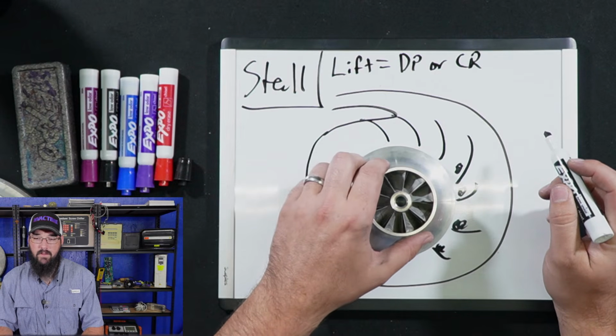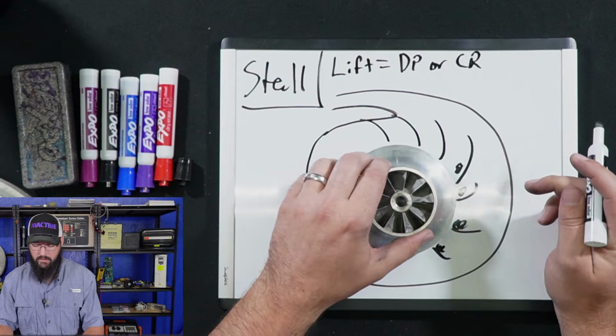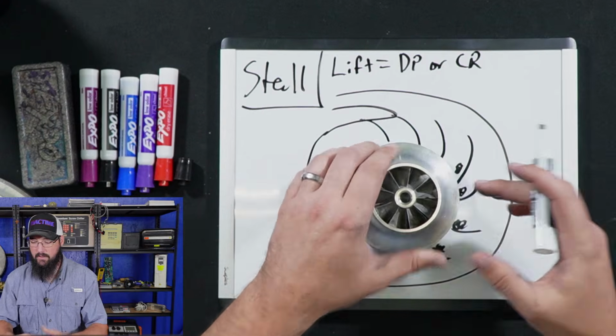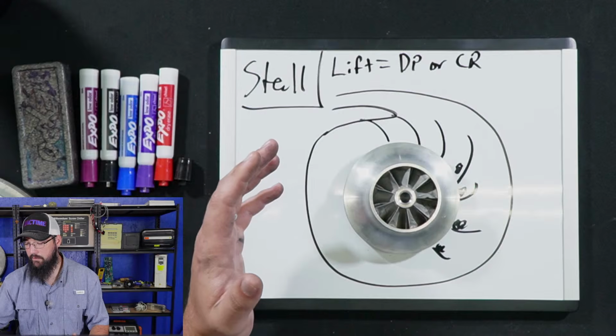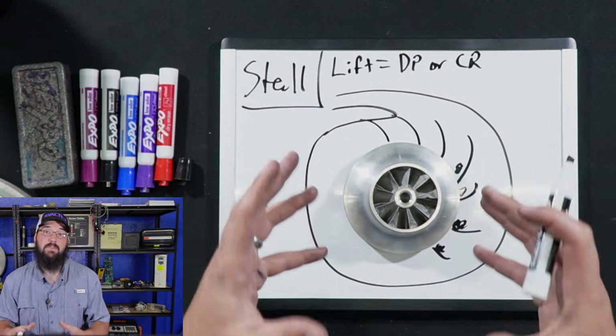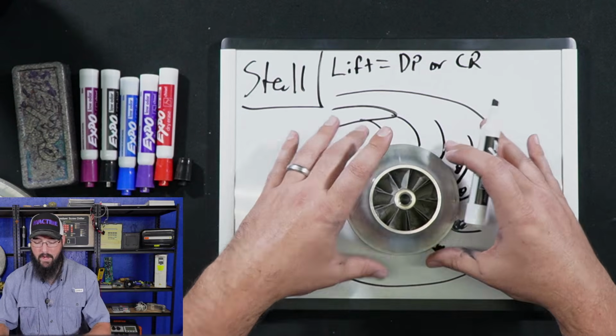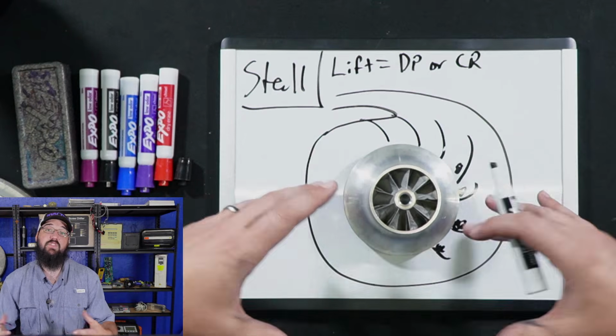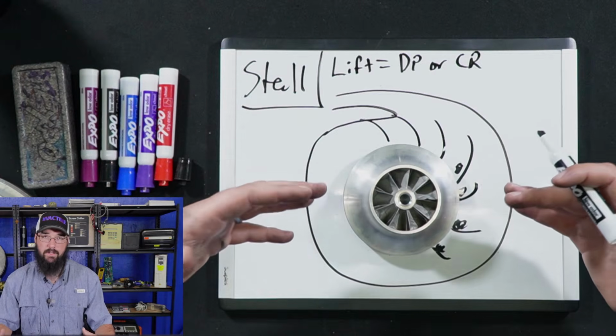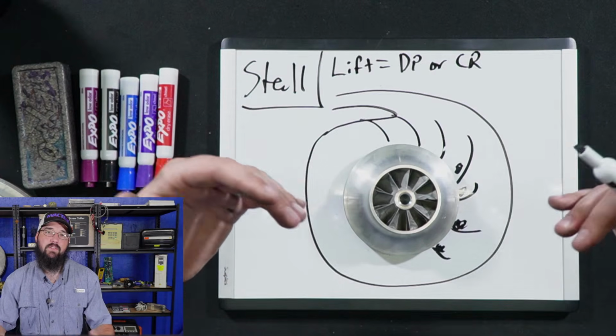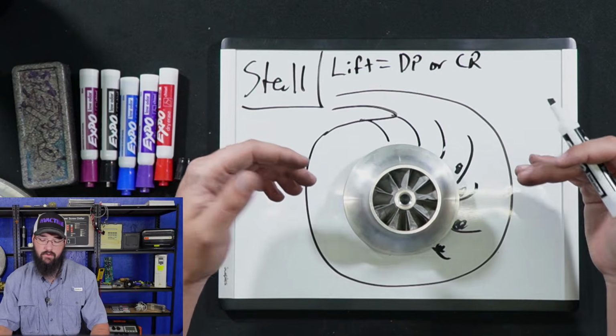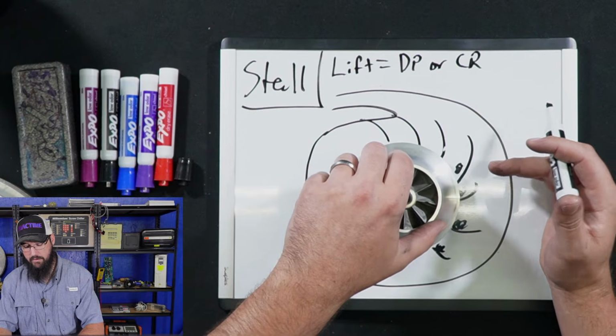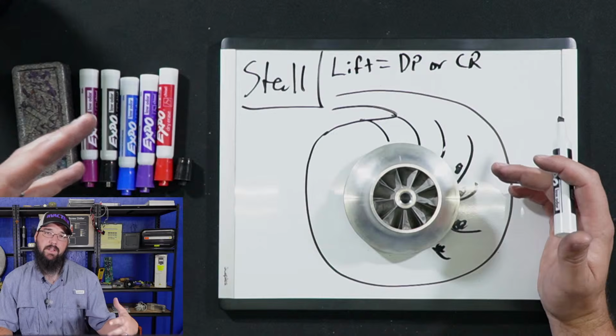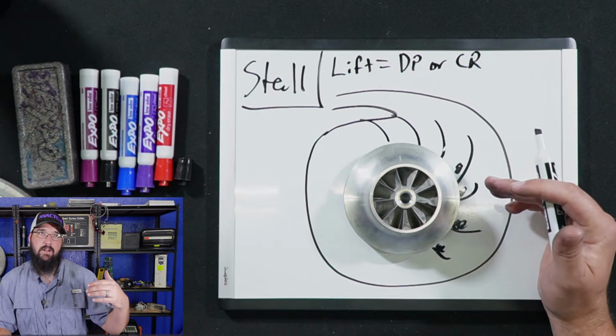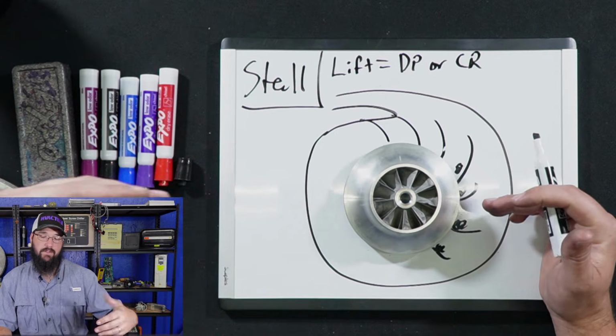So yeah, that's just where we get back into what tip speed is and why a compressor like this will speed up, if it's variable speed, when it detects a stall and surge condition, specifically surge. We're trying to overcome the lift by increasing the tip speed.